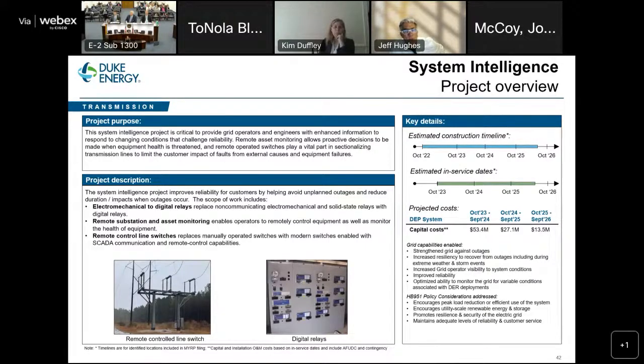Digital relays, the blue boxes in the bottom right picture, are small computers installed in place of traditional electromechanical devices. A relay is simply a device that senses a problem on the transmission grid, generally a fault condition, and sends a signal to a circuit breaker to open and isolate the fault. We're very interested in keeping faults isolated to the smallest possible section of the grid, minimizing impacts on customers.